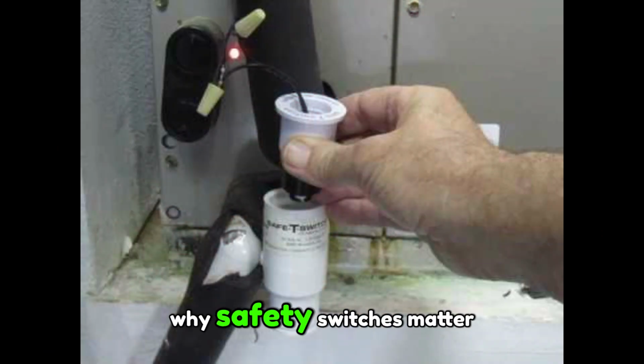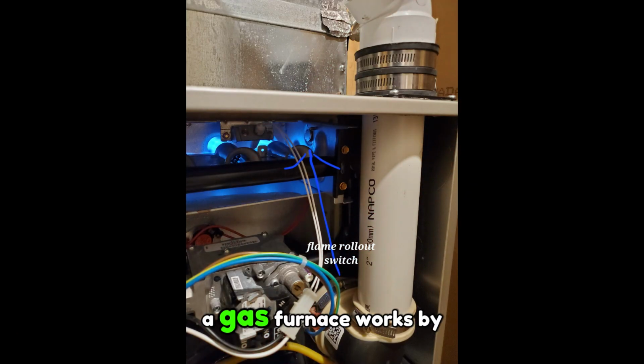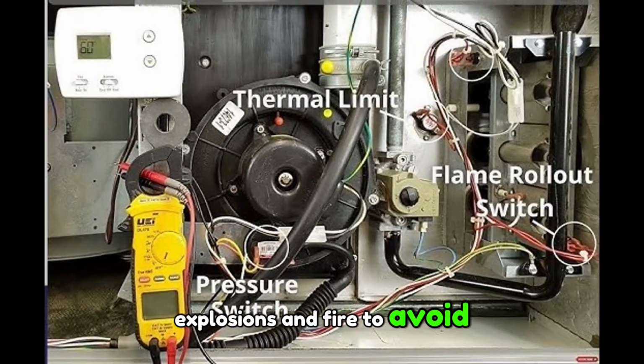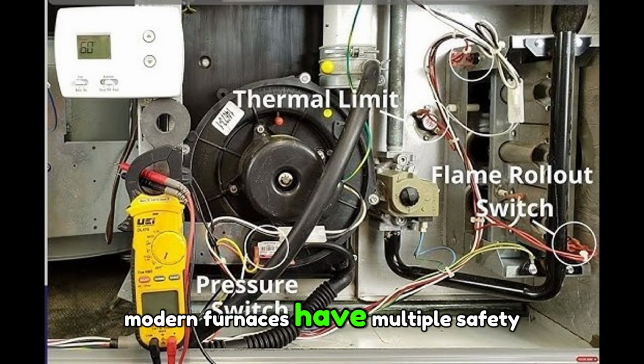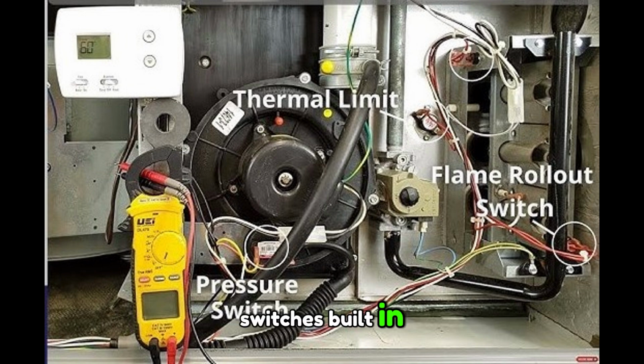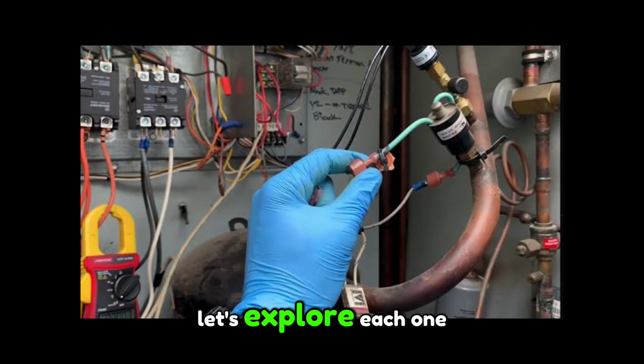Let's begin. Why safety switches matter. A gas furnace works by creating a flame, and with flame comes risk: carbon monoxide, overheating, explosions, and fire. To avoid any danger, modern furnaces have multiple safety switches built in. Each switch monitors a specific part of the furnace and shuts everything down if something goes wrong. Let's explore each one.